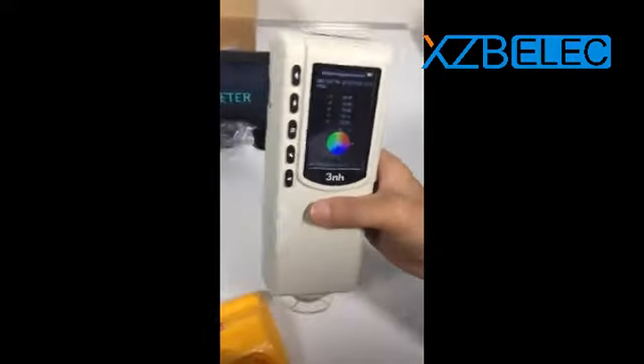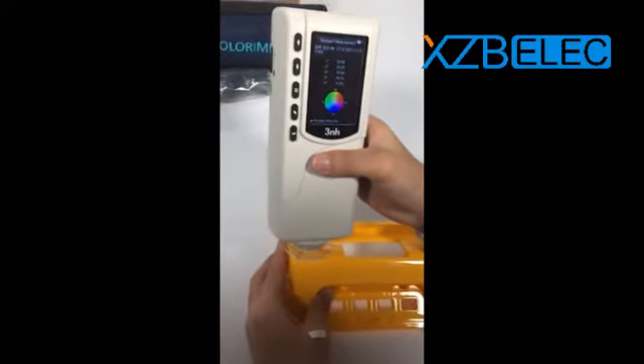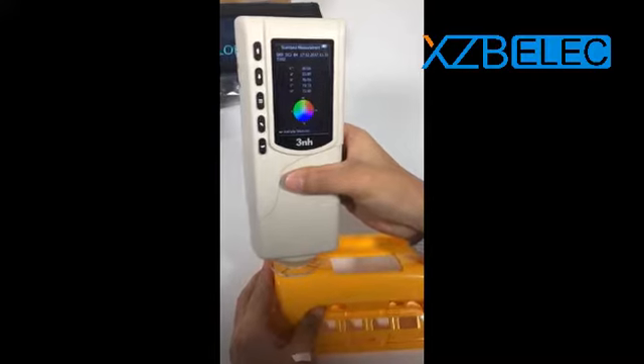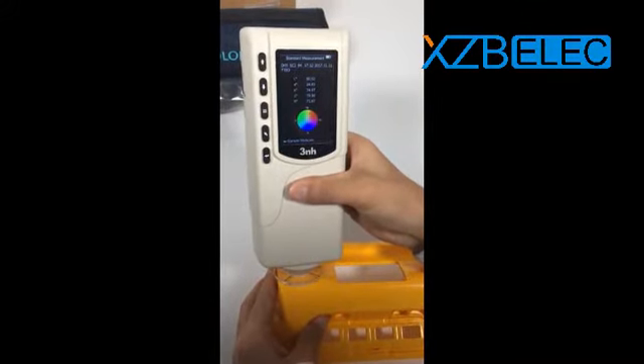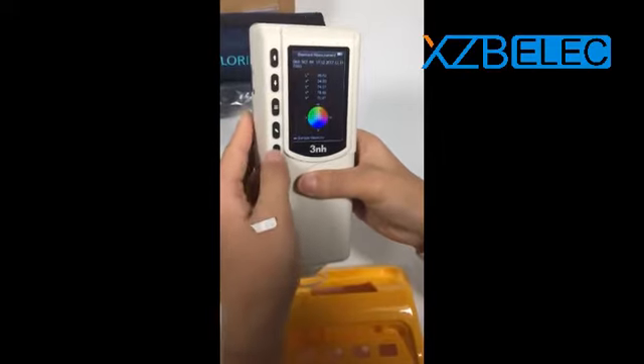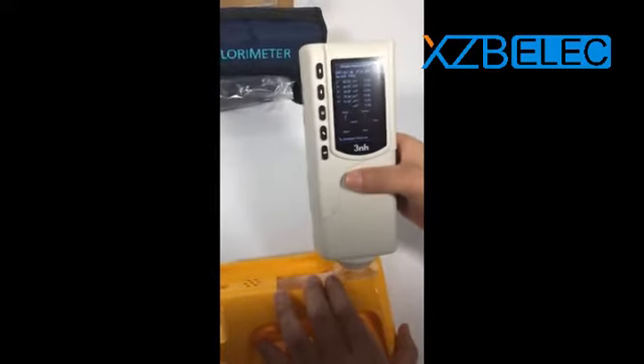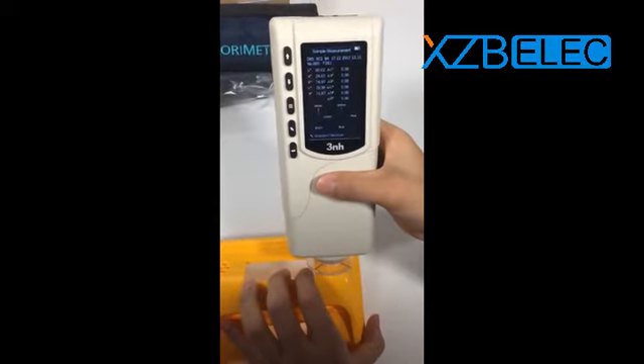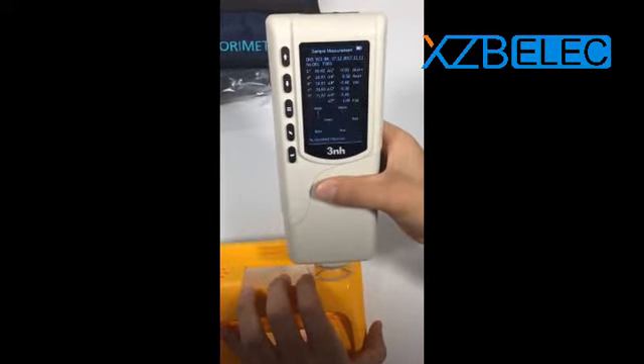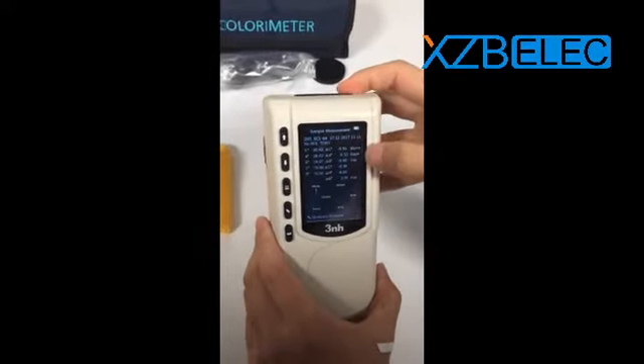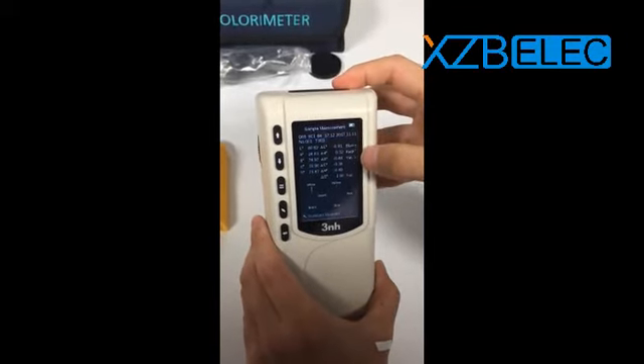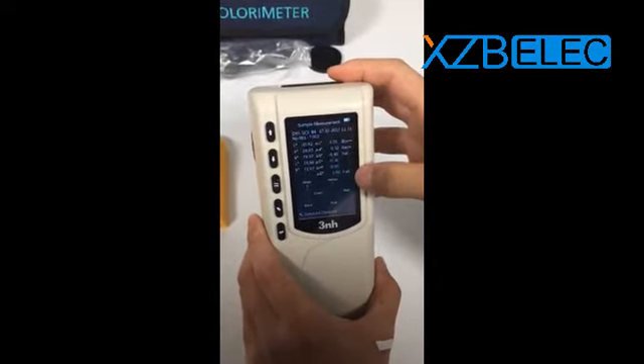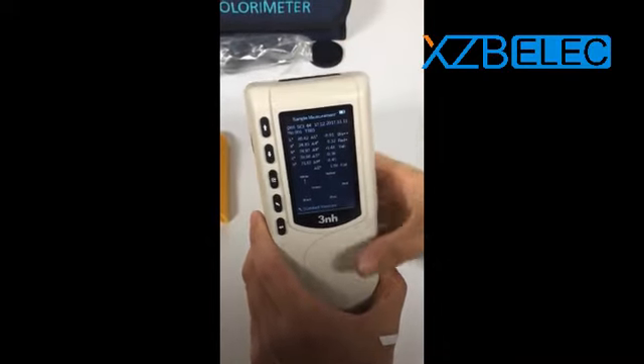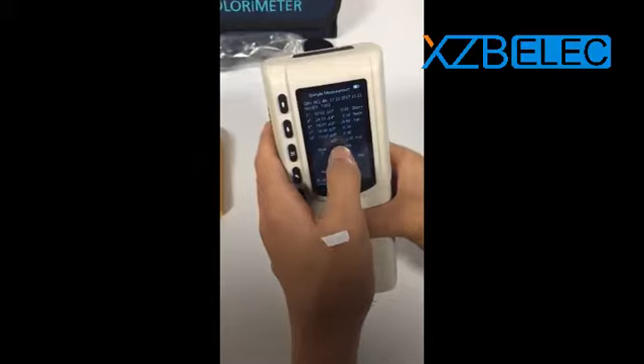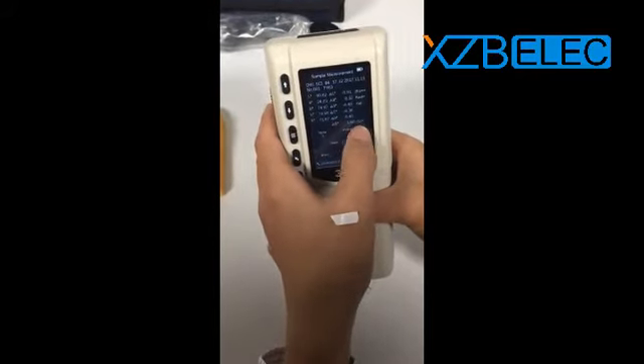First, measure a standard. And then measure a sample. Okay, this is the test result. This is the color offset indication. And this is the test result judgment. The delta E is higher than 1 point, so it should fail here.